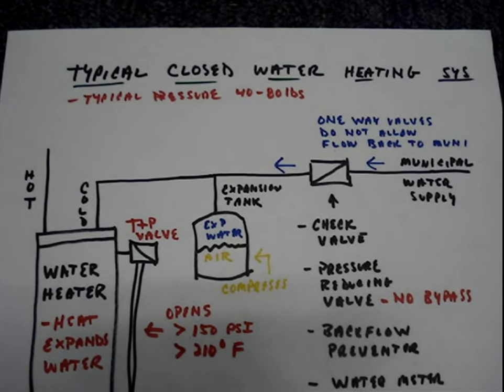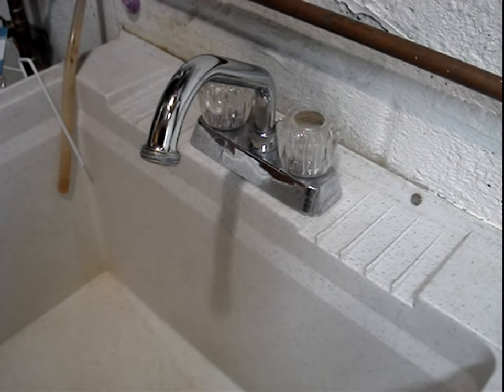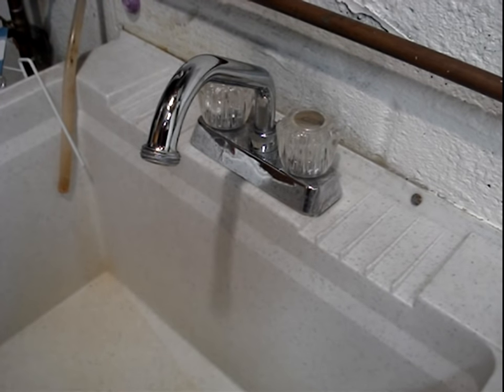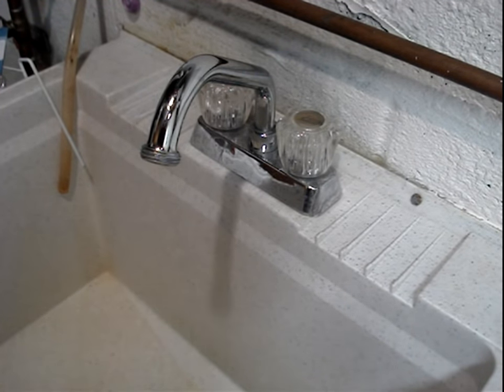212 degrees Fahrenheit at sea level is the boiling point for water. Boiling water coming out of faucets would likely be something that you'd notice. If a thermostat failed and a heater does not stop heating water, then the temperature and pressure valve, if properly working, should open at 210 degrees and stay open until the temperature falls below 210 degrees.